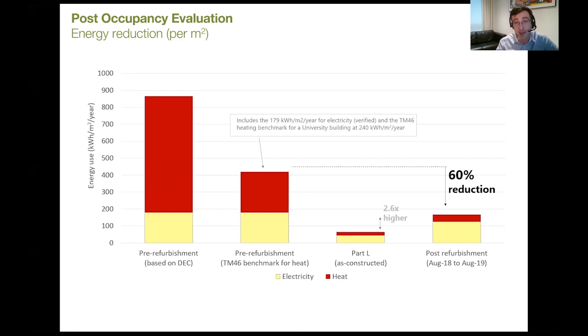And this was per meter squared. I've also put on this graph the Part L performance - the building regulations compliance model that isn't meant to represent reality, but a lot of people often compare what a Part L result gives versus actual. I've illustrated here that the Part L result was 2.6 times lower than what was expected, but this is very common in the industry, for Part L to be 2 to 3 times lower than reality, because the Part L model doesn't include quite a lot of things. It doesn't include any plug loads, for example - it's just looking at regulated components like heat, lighting, and major plant.